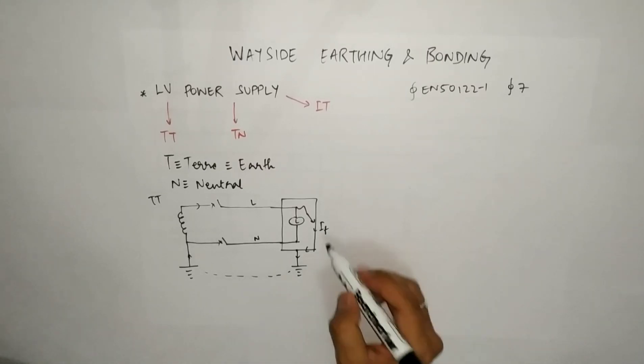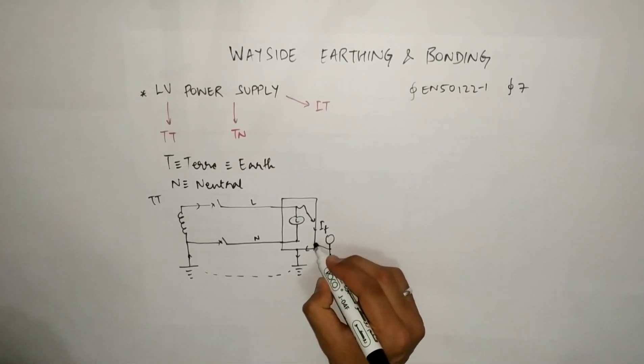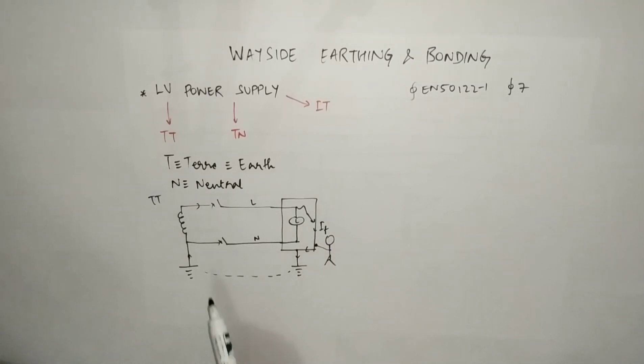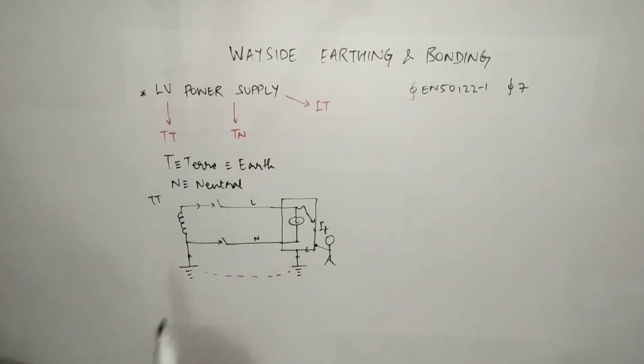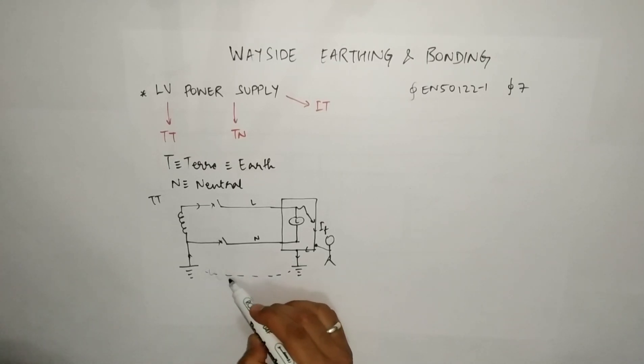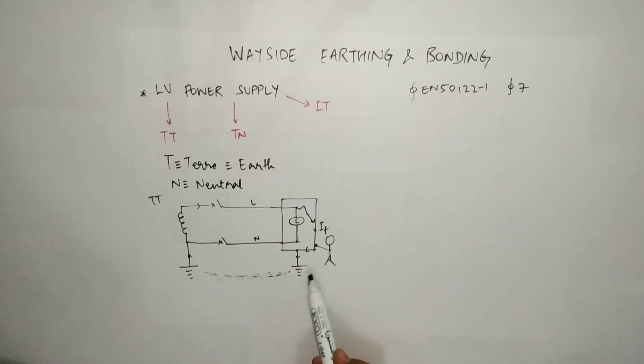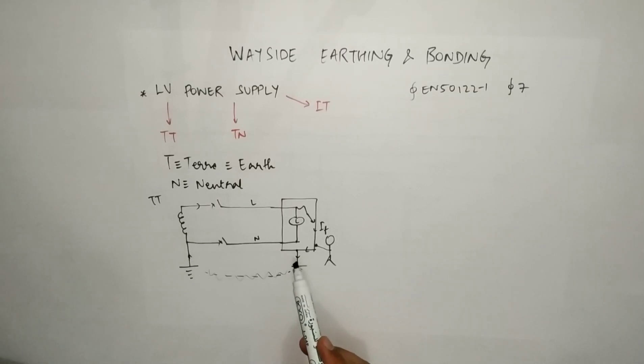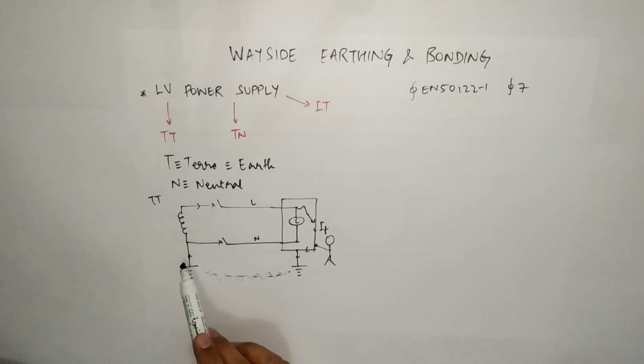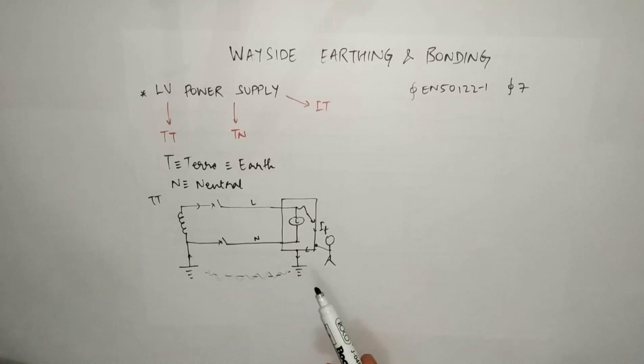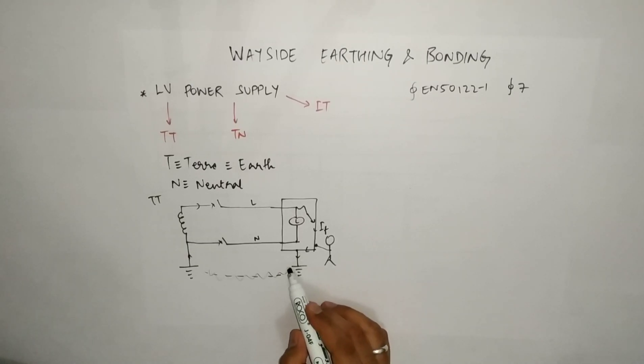If a person is touching and the equipment is connected to earth, he will be safe, but whether the breaker will trip or not we are not sure — we need to design the breaker accordingly. We are not sure about the resistance of this path, as it can vary due to temperature and different seasons. For example, if you design for 1 ohm and after a few months the soil resistivity changes due to summer heat, the dissipation resistance of the earth electrode installed there will change.